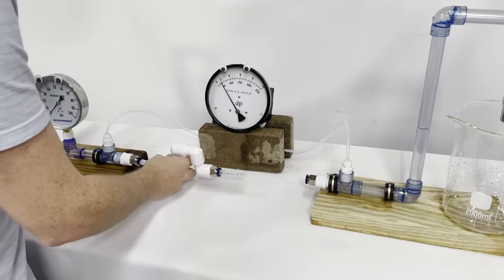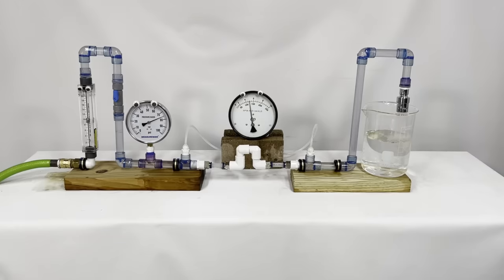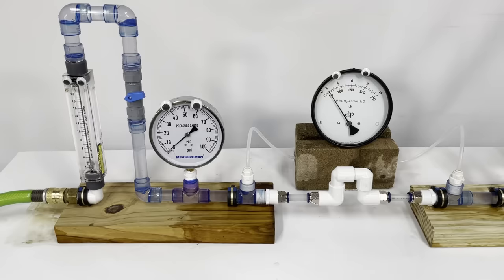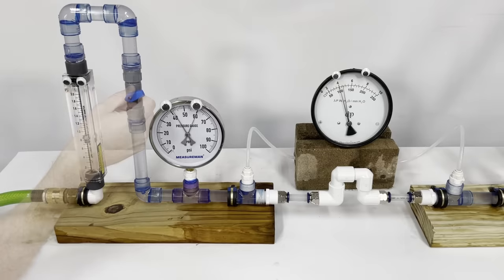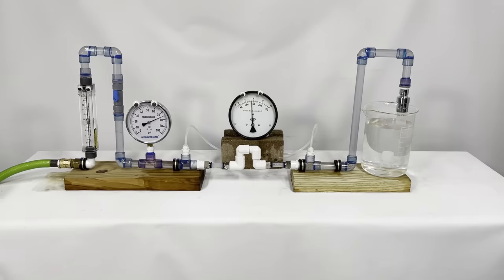As just another example of this, here's a sample pipe with four 90 degree bends. If you were just calculating pressure loss from the pipe flow, you would expect it to be insignificant. Short, smooth pipe of an appropriate diameter. The reality is that, at each of the flow rates tested in the original straight pipe sample, this one has about double the head loss, maxing out at nearly 6 inches of pressure drop at 0.9 GPM.